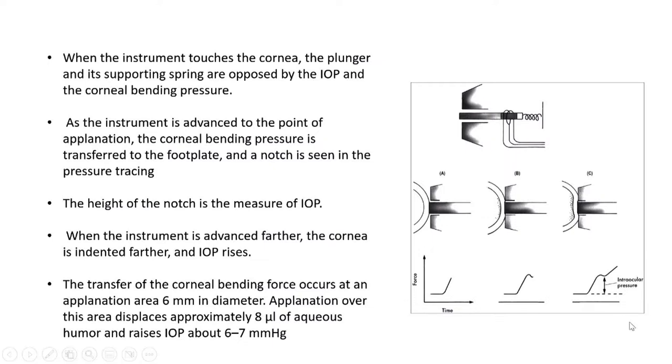And this is what you see in the graph. Initially the pressure rises, and when you see this dip over here, this is the point where the foot plate has taken over, and you get the true IOP reading. The height of this dip is the IOP reading.